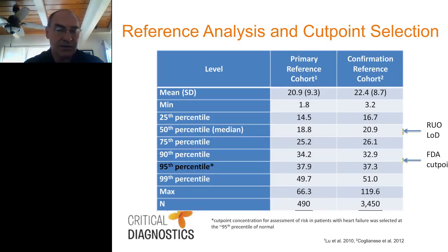Now that's an individual that probably has pre-symptomatic disease, which we've learned since we did this, but again, these are self-declared healthy individuals. But the FDA wanted us to find a cut point that could be used to provide guidance to physicians in how to use the test. So we elected to use a strategy of defining that cut point based on higher concentrations in the normal asymptomatic population.